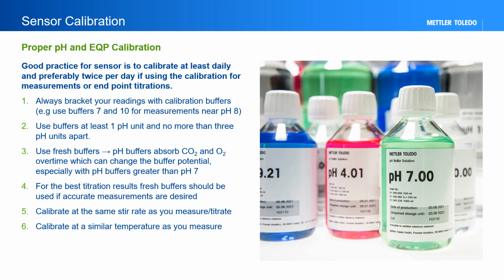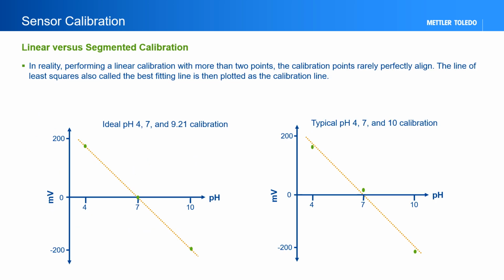Calibrate your sensors at the same stir speed at which you measure or titrate. Also calibrate at the same temperature as you measure or titrate. These last two steps help ensure consistent ion activity from standard to sample. Pictured is an ideal linear calibration of a pH electrode using pH buffers 4, 7, and 10. In reality, when performing a linear calibration with more than 2 points, calibration points rarely perfectly align. The line of least squares, also called the best fitting line, is then plotted as the calibration line.